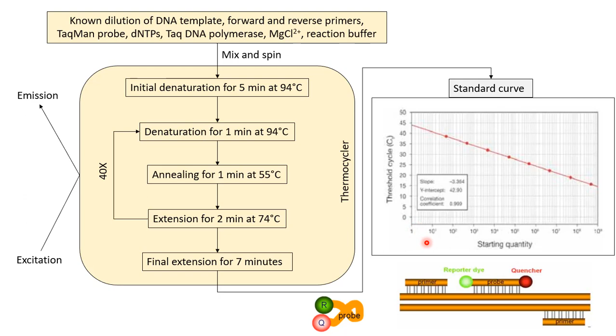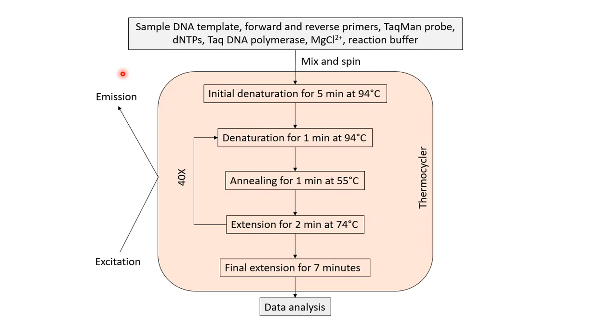So for quantitative purpose, we have to follow this rule. If we get low CT value in a real-time PCR, it means that sample contains high concentration of DNA, and if we get high CT value, then it means sample contains low amount of DNA. After the instrument is calibrated, we can proceed with our sample. Here also the procedure remains same as we have discussed earlier, except that instead of known DNA, here we will add our sample DNA. As the PCR proceeds, DNA concentration is increased and we start to see fluorescent signal in the computer attached with the PCR machine.